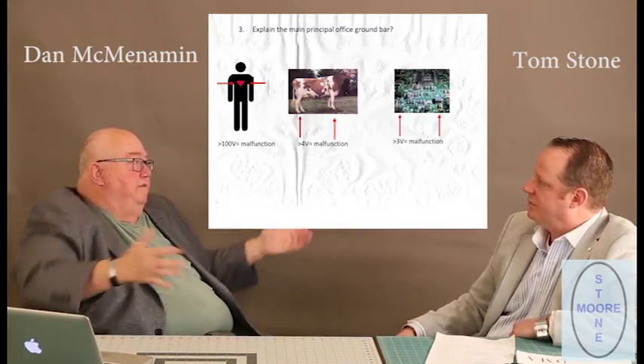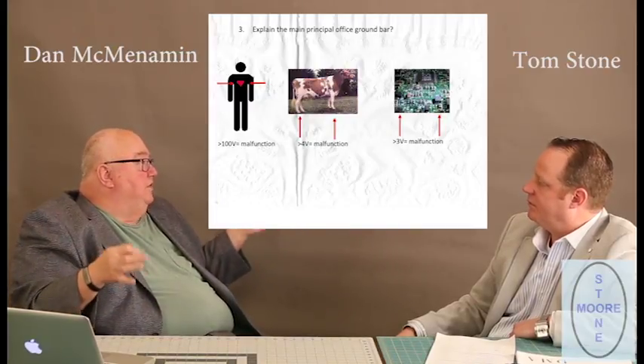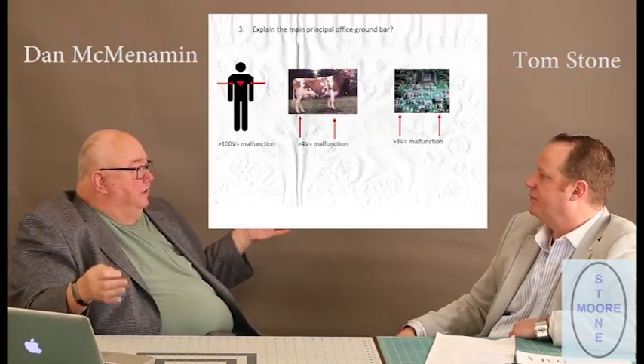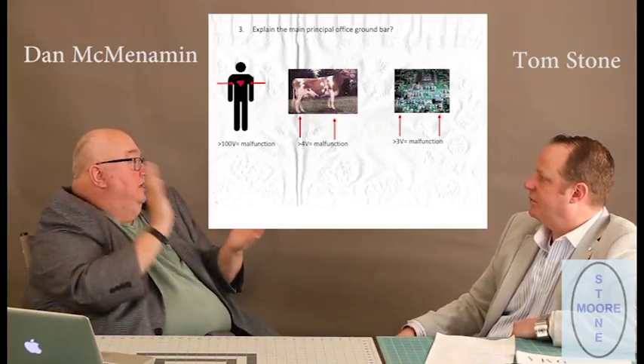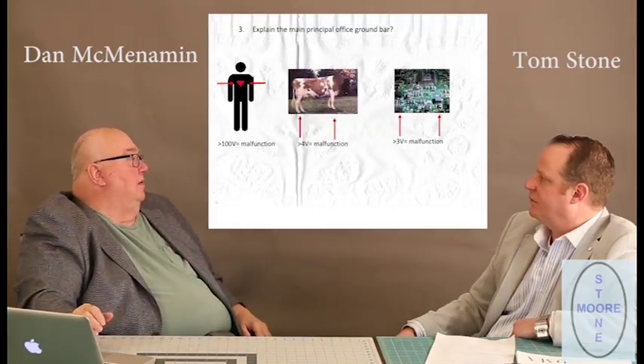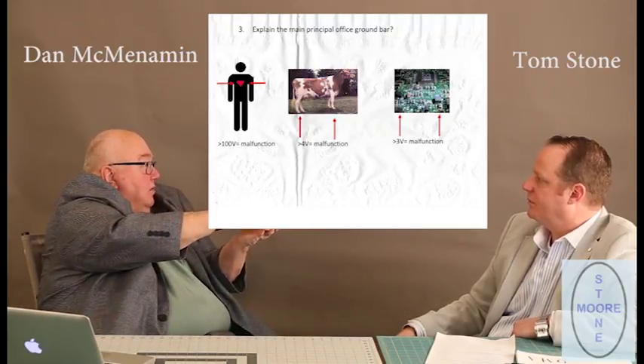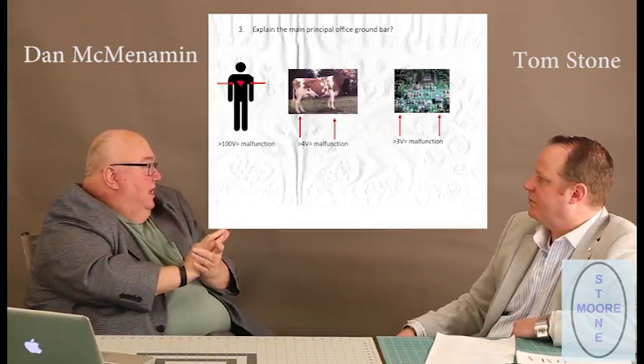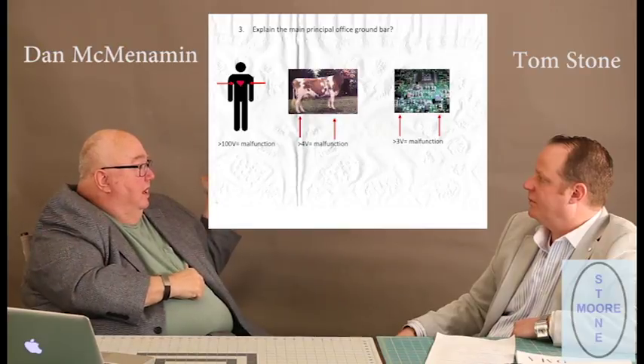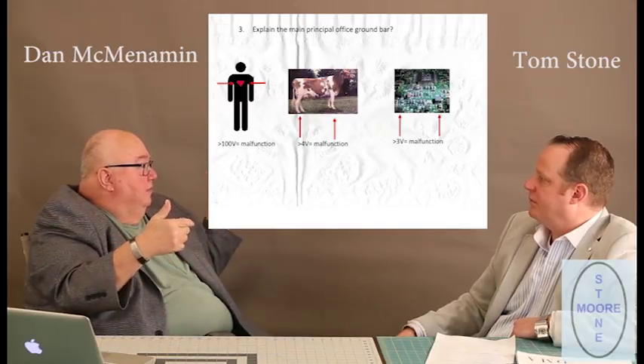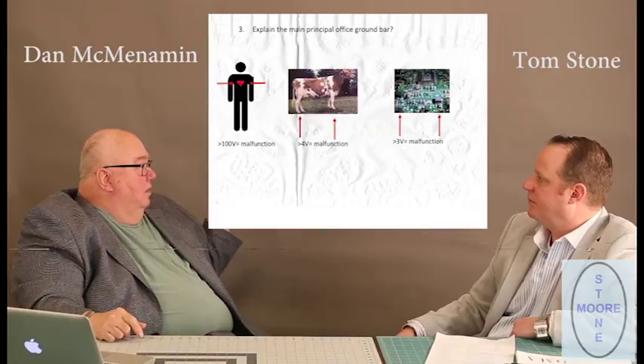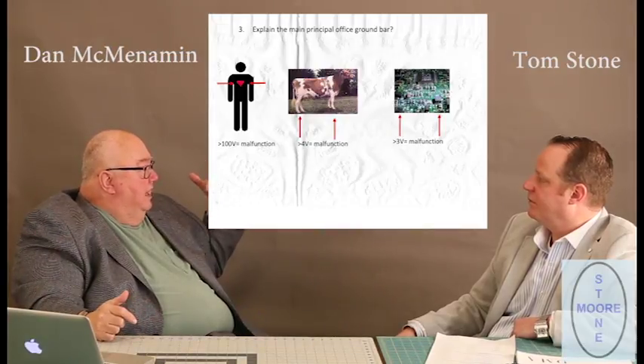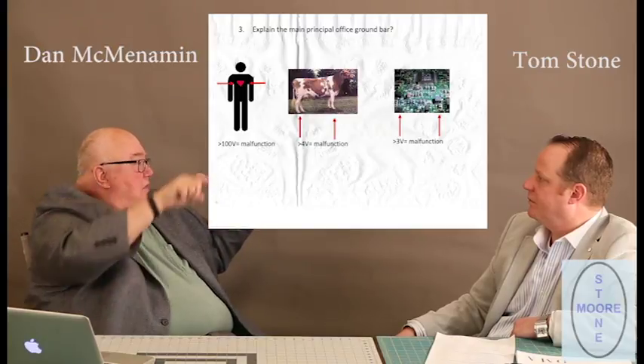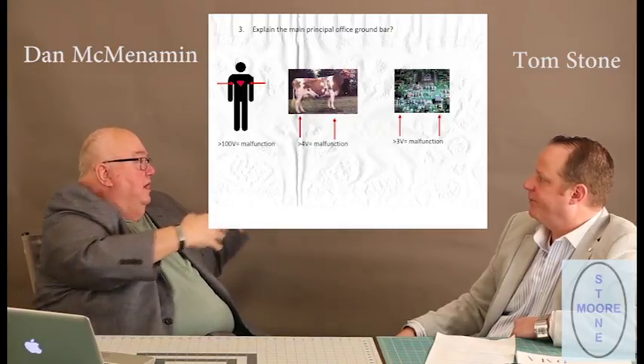Now, take that same principle into the central office in a power plant. 48 volts isn't going to shock anybody. But the most common failure in a central office is a ground fault, where either a piece of equipment fails internally and shorts to chassis ground, or a cable gets pinched in a cable tray, or somebody ran it around a threaded rod and it dug in. You want to be able to trip the circuit breaker upstream at the source, so that you're not arcing and starting a fire in the cable tray or in the equipment. So the power plant needs a ground source at that point to give the circuit breaker something to fault to, to cause that breaker or fuse to open up.